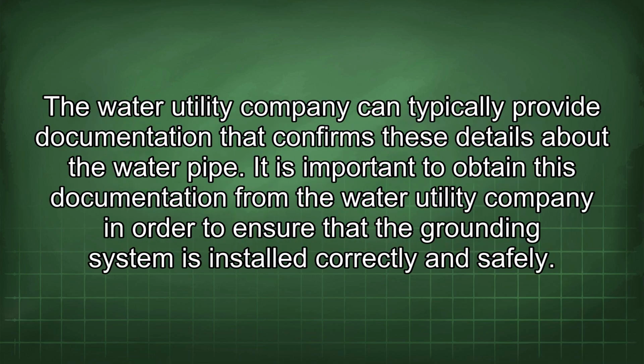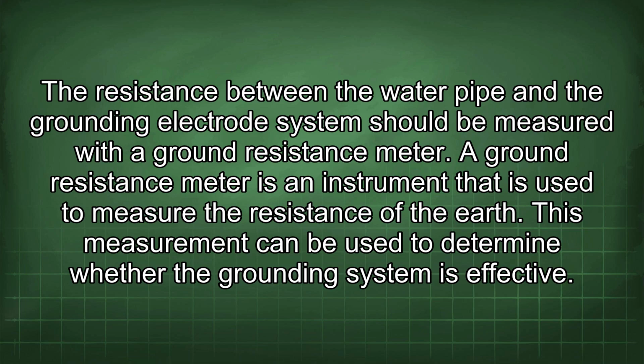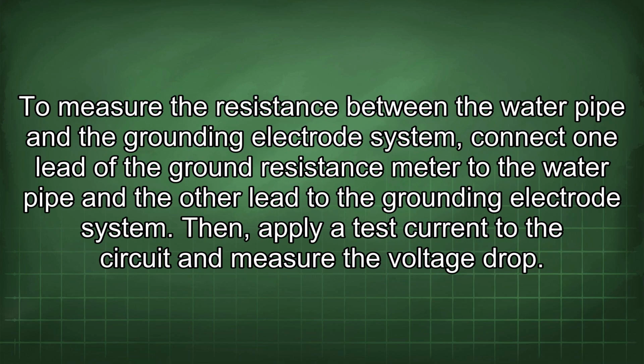The water utility company can typically provide documentation that confirms these details about the water pipe. It is important to obtain this documentation from the water utility company in order to ensure that the grounding system is installed correctly and safely. The resistance between the water pipe and the grounding electrode system should be measured with a ground resistance meter. A ground resistance meter is an instrument that is used to measure the resistance of the earth. This measurement can be used to determine whether the grounding system is effective. To measure the resistance between the water pipe and the grounding electrode system, connect one lead of the ground resistance meter to the water pipe and the other lead to the grounding electrode system. Then apply a test current to the circuit and measure the voltage drop.